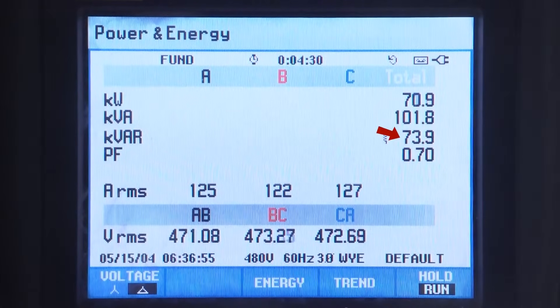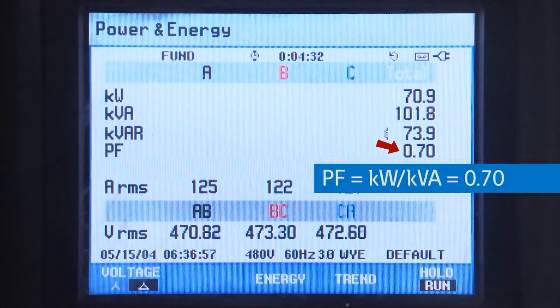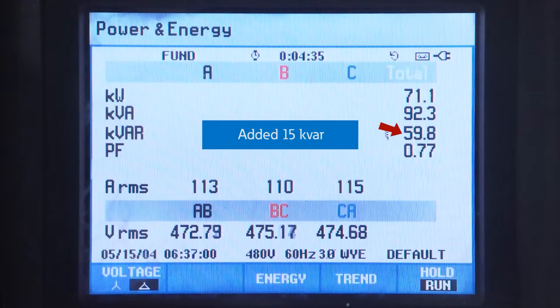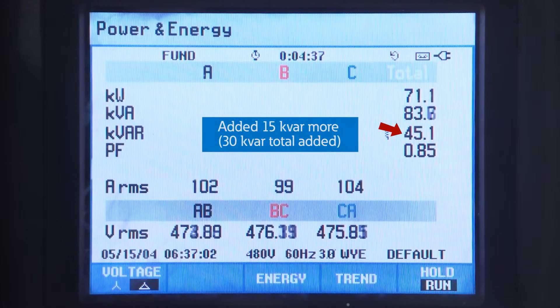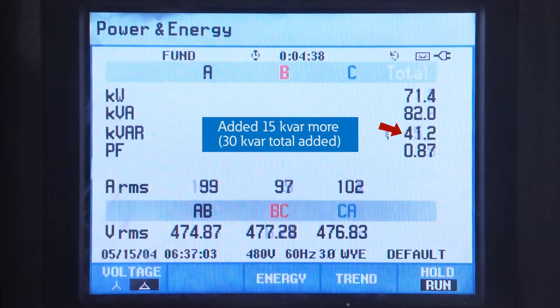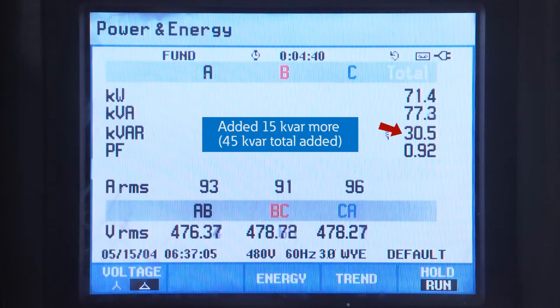Loads take the real and reactive power that they need. For this case, the load is 71 kilowatts, 73 kilovar, and 101 kVA with a 0.7 power factor. From a system standpoint, the addition of capacitors, or VARs, improves the ratio of real power or kW and apparent power or kVA upstream from the capacitor location by reducing the net reactive power or kVARs. We are adding 15 kVAR at a time until we negate the 73 kVAR of the load. Notice that when we overcompensate with capacitors, the kVAR goes back up, the current goes back up, and the power factor goes down again, but is shown as a leading power factor.